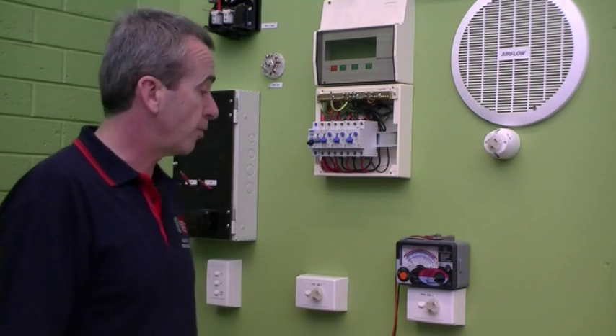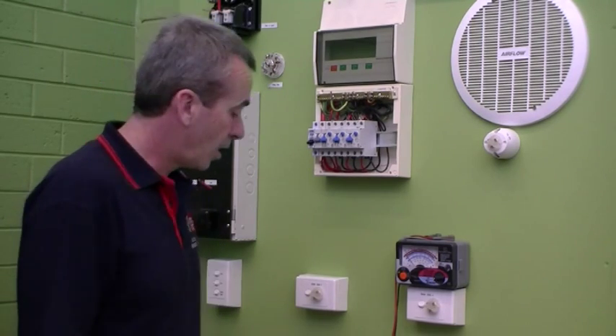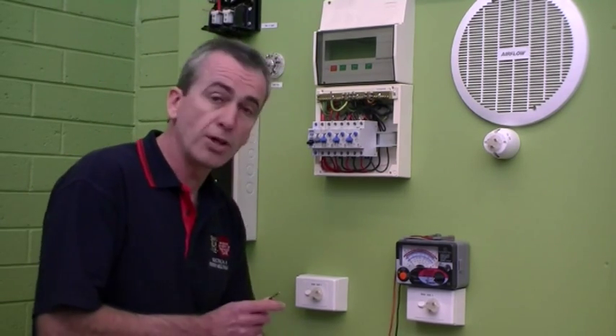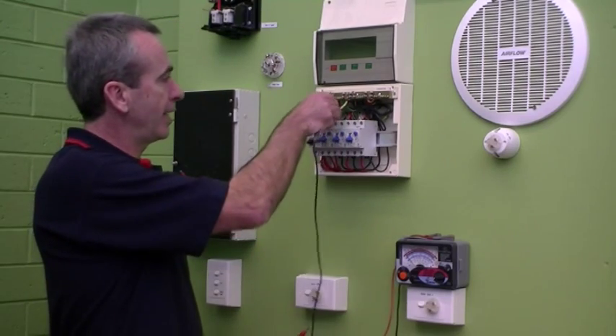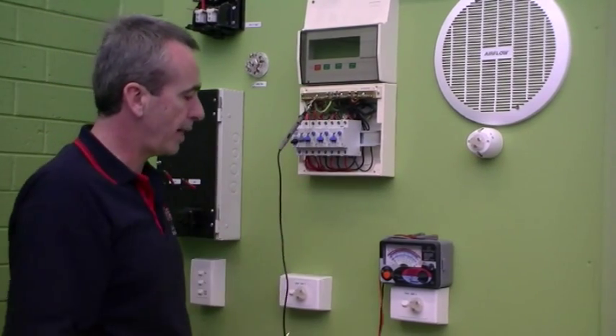And to do this test, I've got the meter already set on the low ohms range. I've already tested the meter to make sure the batteries are good and it's operating properly. I'll take one of my leads and connect it to the earth bar. So I'll connect that to the MEN link. That is still connected to the earth bar.